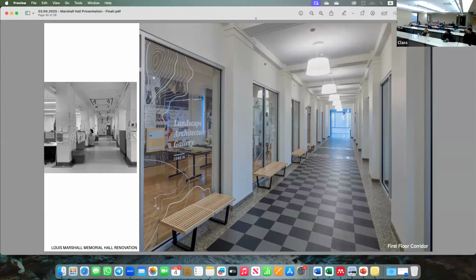So is the alternative ductwork fed up from the roof or in from the walls? Basically what we did is we fed down on either side. We have ventilation ducts, and the ventilation units are up on the top floor, and that duct has to get throughout the whole building. So there are risers on both sides, and both ends, that come down and feed out to the spaces. Then you have the heat pumps, which are in or close to the areas they serve, with their own supply and return duct that's more limited, just going into that one little zone. On this side of the hallway, there's a heat pump closet in this room right here that has a heat pump feeding this area, and another one that comes off and feeds this whole area. Same thing on the other side. So you have 4 heat pumps feeding this part of the floor, and on the other side a similar number. Some of them are on this floor but actually go up to the second floor - that was more uncommon. But again, we had about 85-ish heat pumps throughout the building.